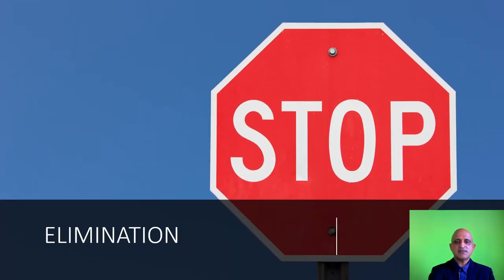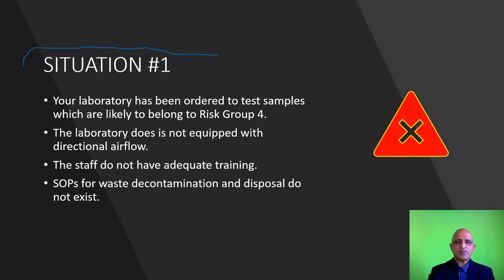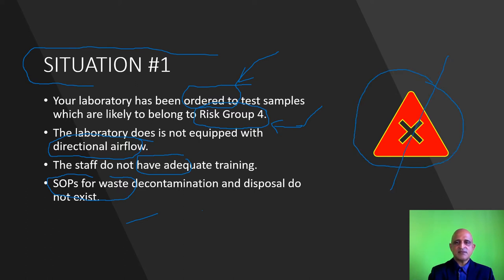The first control is elimination. Consider this situation: your laboratory has been ordered to test samples which are likely to belong to risk group 4, such as during a pandemic. However, your laboratory is not equipped with directional airflow, you do not have a containment facility, staff do not have adequate training, and SOPs for waste decontamination and disposal do not exist. With these multiple limitations, it is highly likely there will be a breach of containment. In this case, we resort to elimination — a collective decision not to proceed with the laboratory procedure.